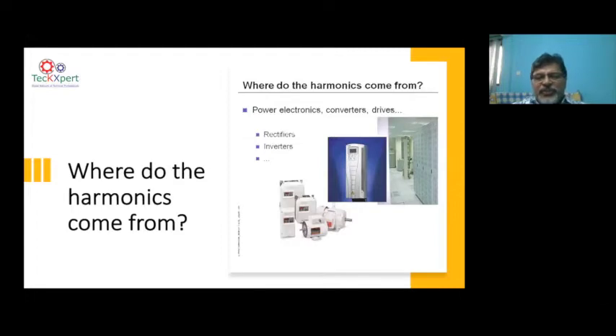So where do the harmonics come from? As I said before, all power electronics are the culprits of harmonics. When I say power electronics, rectifiers and inverters are the building blocks of AC drives. Here it shows an AC drive, which has a set of diodes at its front end. It takes the AC and converts it to DC through the diodes, and there's a DC bus which holds the voltage with a capacitor, and then that voltage is inverted to the required voltage and frequency for the motor to run at variable speed. So you have a rectifier and an inverter. Both are power electronics, so these are all nonlinear loads and naturally produce harmonics. Go to the next.